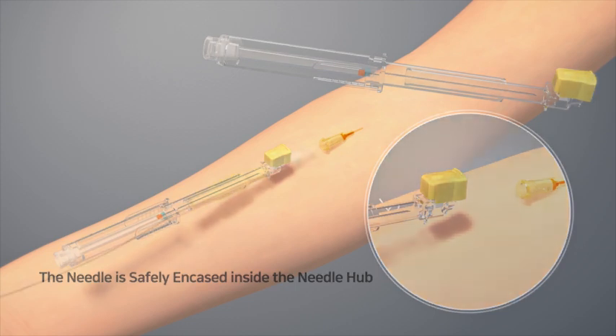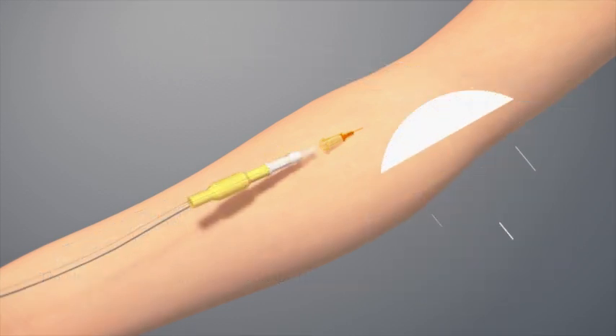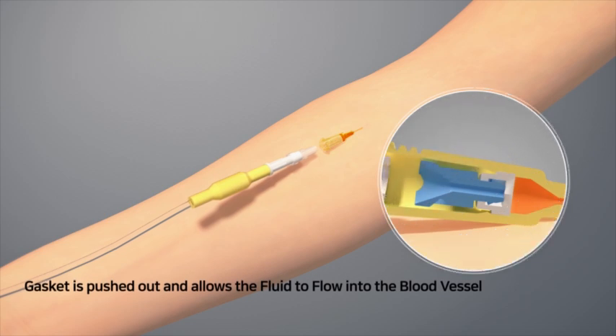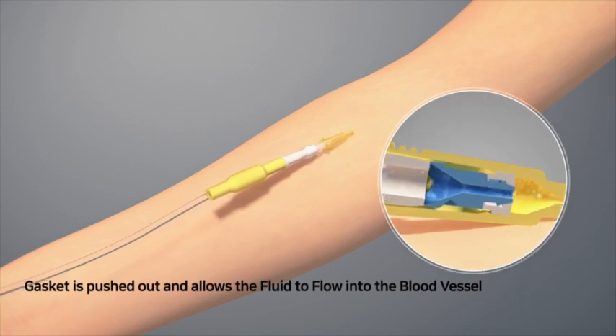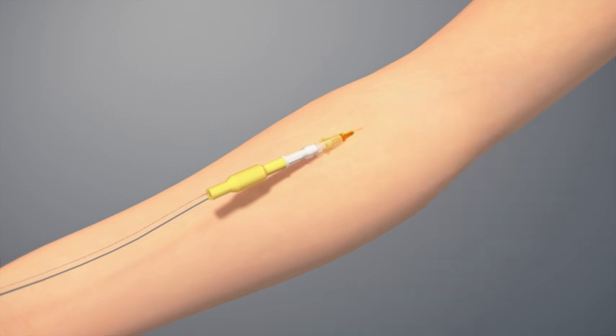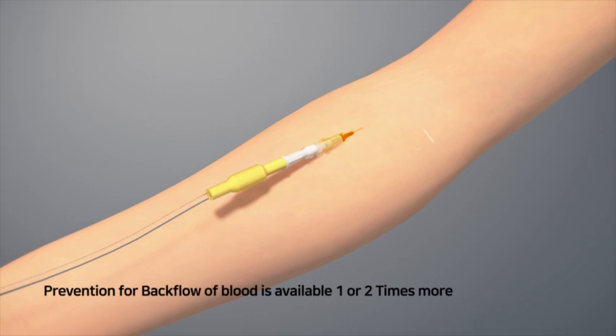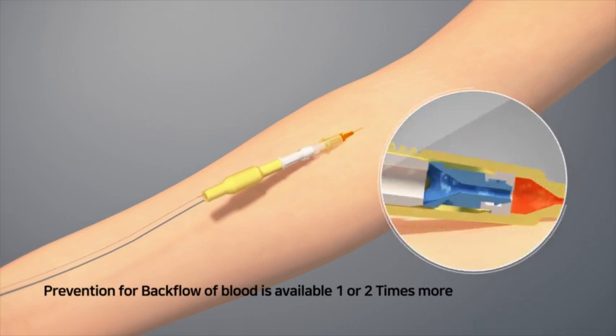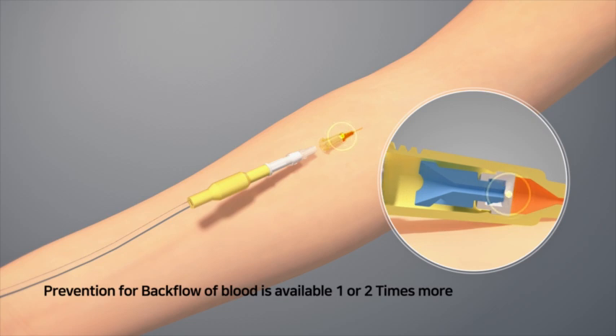It's time to insert the connecting tip of the supply tube to the catheter. The blood-stopping holder will be pushed to open the gasket and let the fluid flow into the blood vessel of the patient. Even if the fluid set has to be changed due to the restoration of blood reflux, just disconnect the connecting tip from the catheter. The blood-stopping holder in the catheter will be pushed back to close the gasket to stop the blood from coming out 1 or 2 times before a new fluid set is connected.